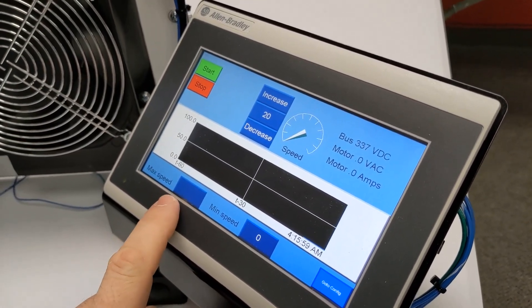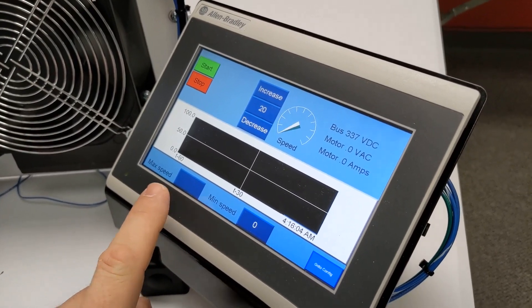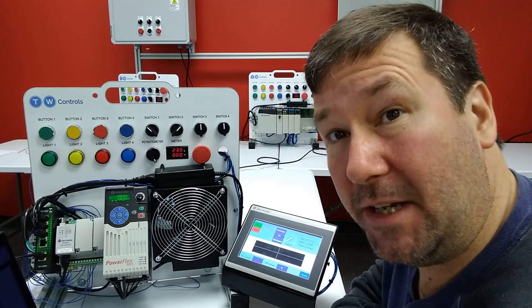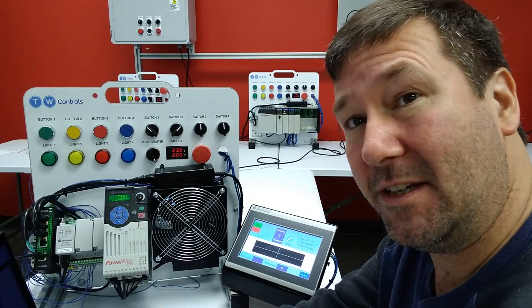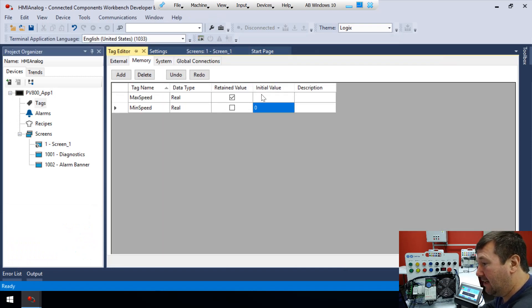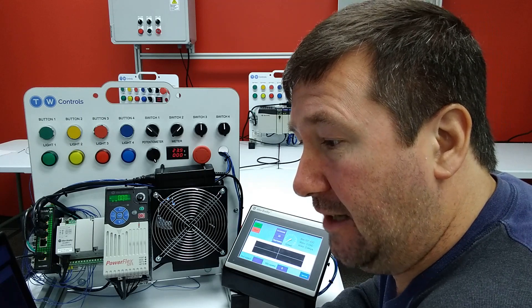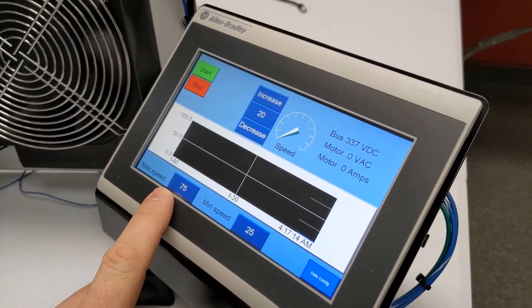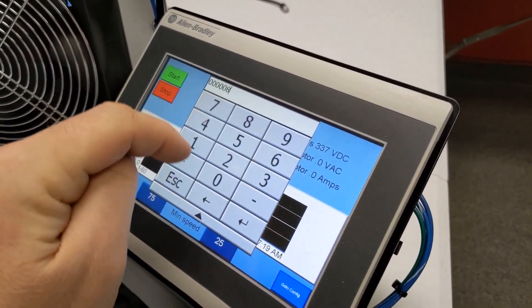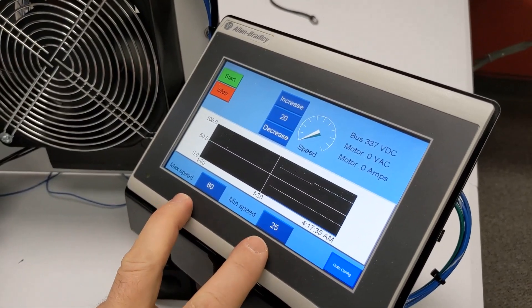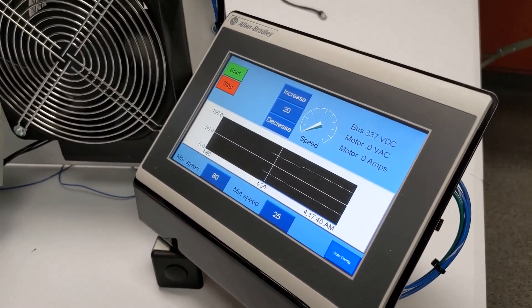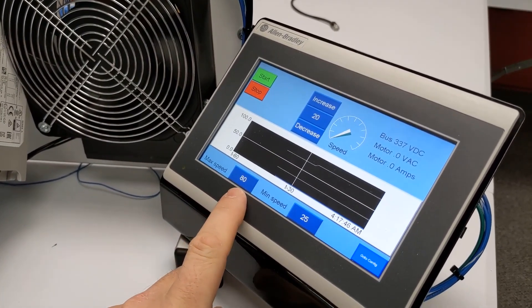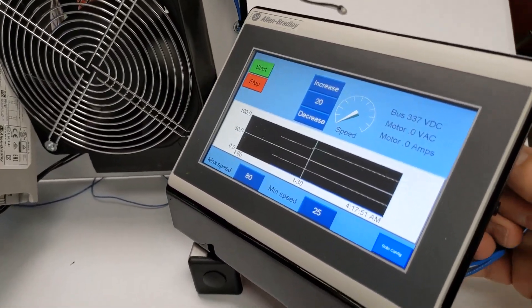Now let's download this program. Now notice, well, one, when we download, we lost that retained value. So every time you download, you lose the retained value. But now that we have an initial value into our min speed, it does show zero. So now that we know we want our min and max speed to be 25 and 75, at least initially, we can put those in there so that we don't have to enter them every time. So we're going to go back to tags and our initial value for our max speed is going to be 75 and our initial value for a min speed is going to be 25. So let's go ahead and download that.